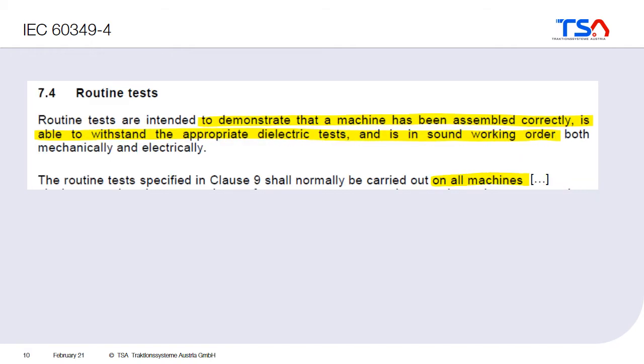Additionally, on every machine which is manufactured, a routine test is also done. This routine test should demonstrate that the machine has been assembled correctly, that it is able to withstand the dielectric test so the insulation is okay, and that it runs smoothly. It is not the full program of the type test — it is only a reduced test — and it should just confirm that the machine is okay and can be delivered. This should be done on all machines which are delivered.